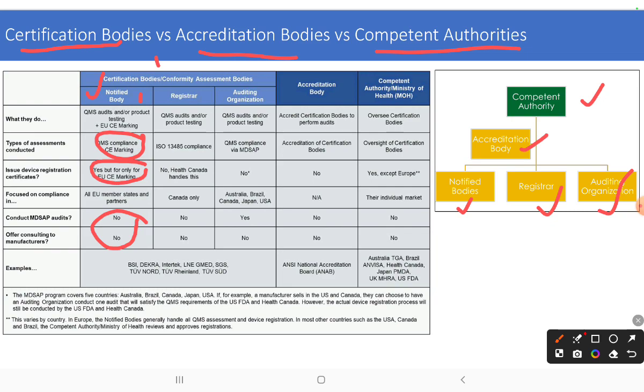Now come to a registrar. The registrar is the same thing: QMS audit and product testing. They check compliance against ISO 13485. Do they issue a device registration certificate? No, Health Canada handles this, Canada only. So the word registrar is used in Canada only.